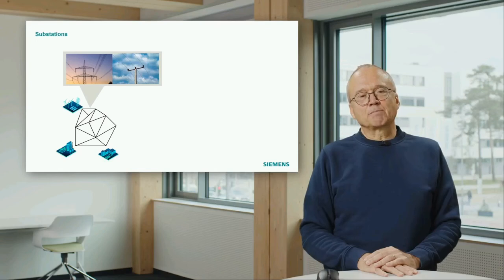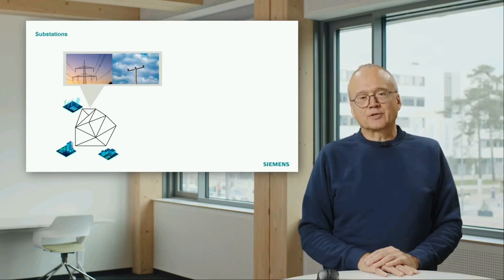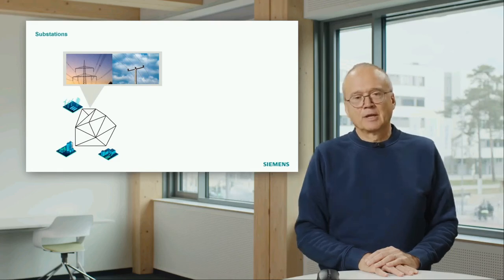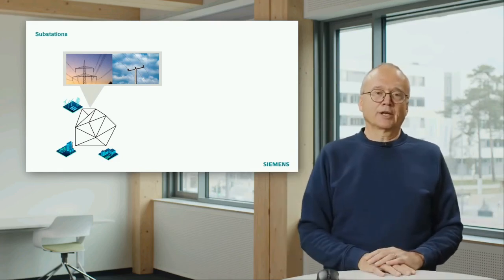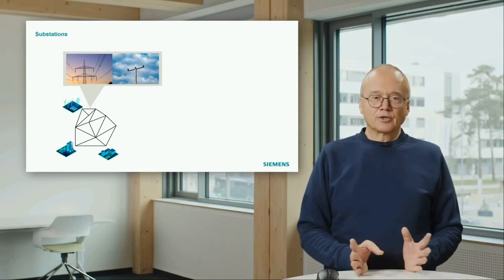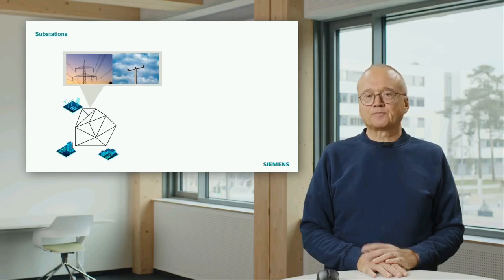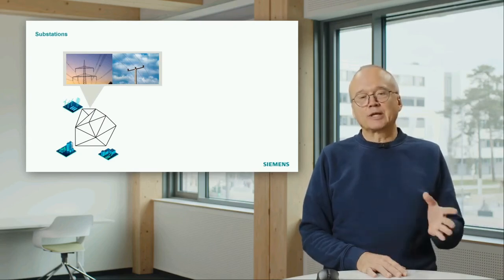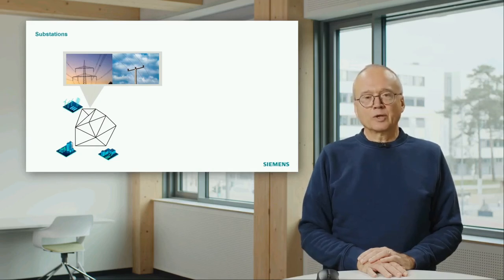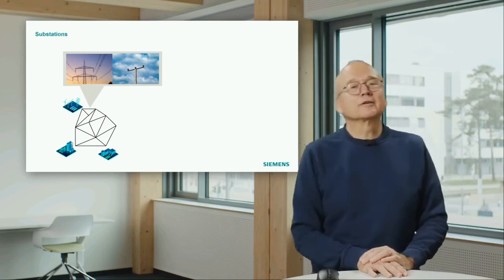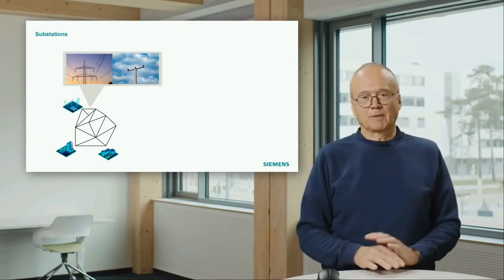What you also see in this picture is that every one of these 3 conductors of the system consists of 4 individual wires. That is state of the art for extra high voltage. It reduces the electrical field strength around the conductor. That's why it's a normal case for an extra high voltage line. On the right-hand side, you see a medium voltage distribution overhead line. In this case, 1 system, that means 3 conductors. And there we use just single conductors for the individual phases because the field strength is much lower there.